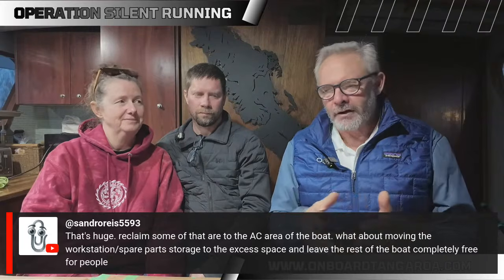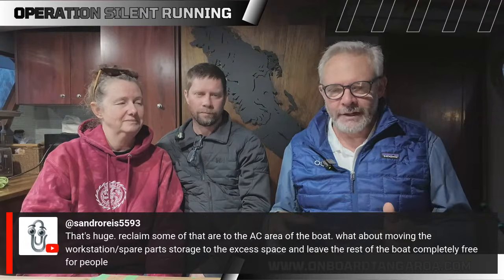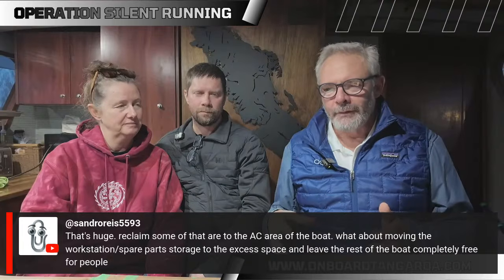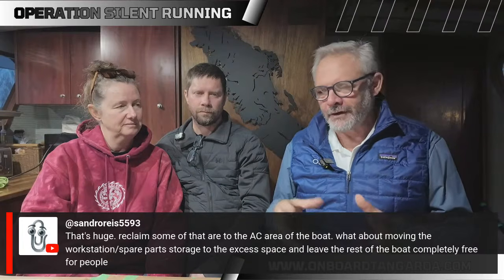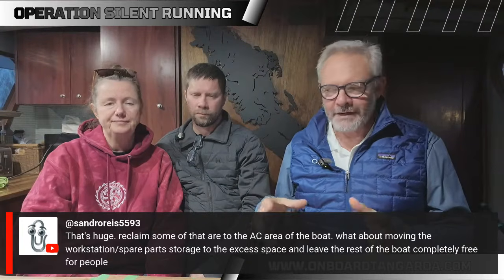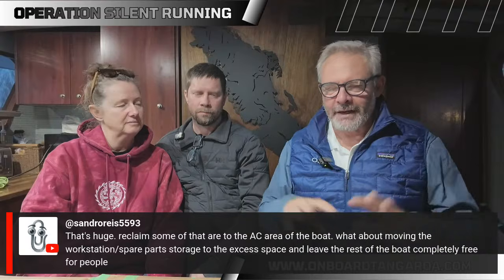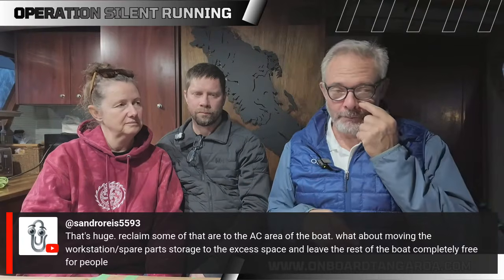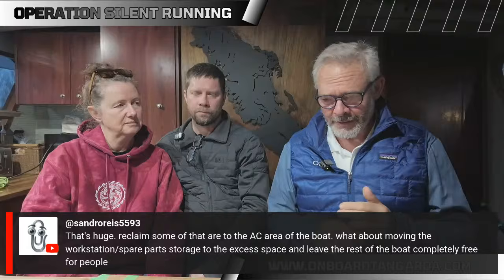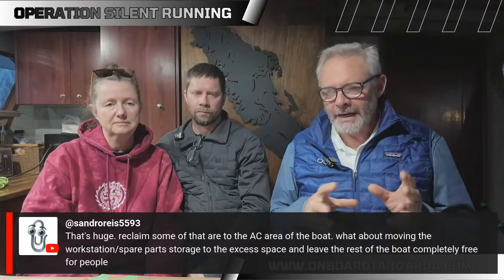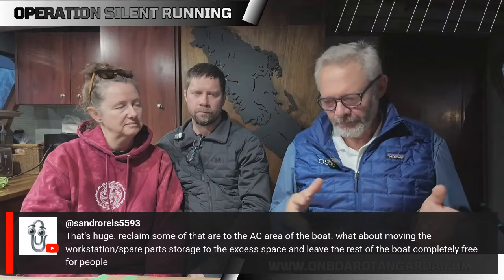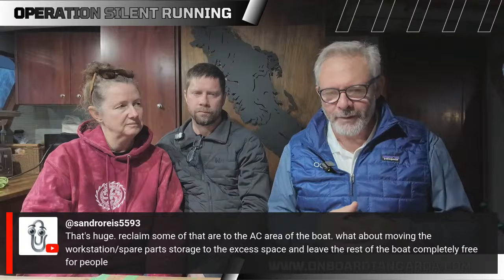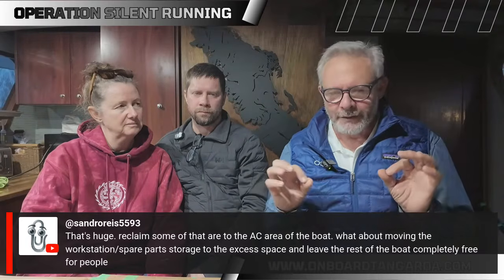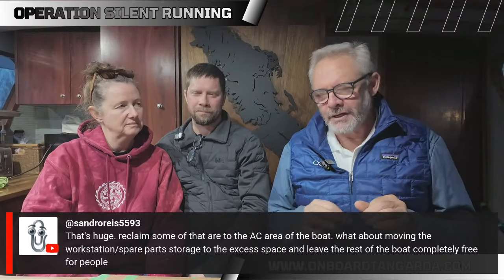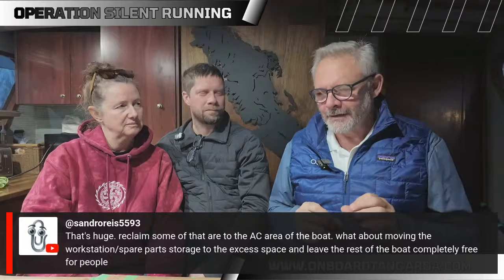In our conversations with all the generator companies, we went to them wanting four generators that all have sound enclosures so we can manage heat through the exhaust. That way we can keep the ambient room temperature pretty cool, around 35 degrees, but use air to manage the temperature, and the batteries will live at a nice temperature for operational purposes. Hallelujah. But all the generator guys came back and said, good God, that's going to cost a fortune to have ideal sound shields.